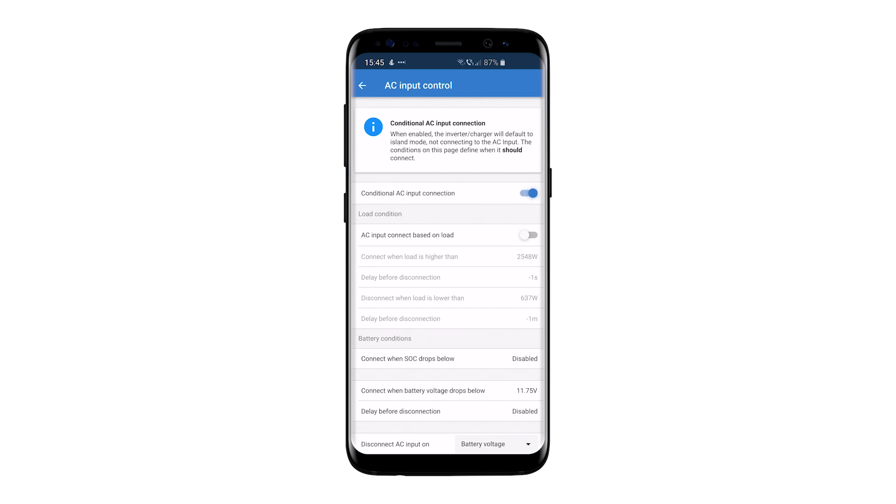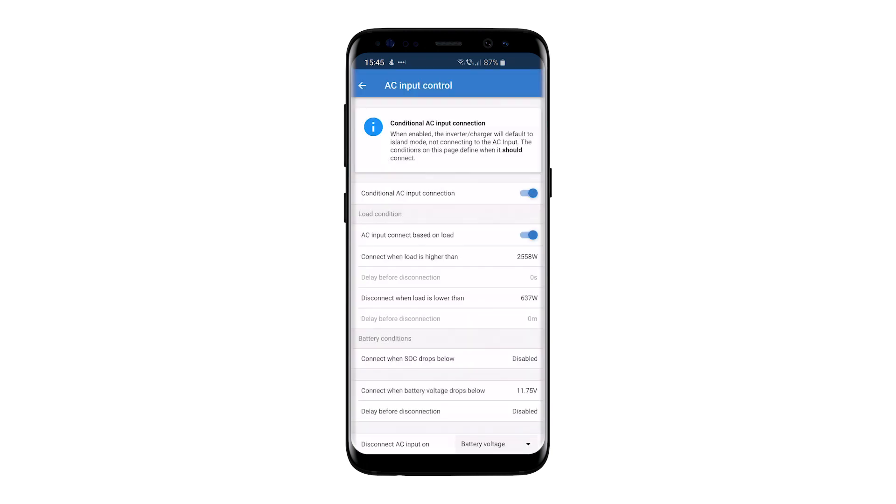Enabling AC input control makes the device purposely ignore the grid, and the settings let you define under which high load and/or low battery conditions it should connect to the grid.